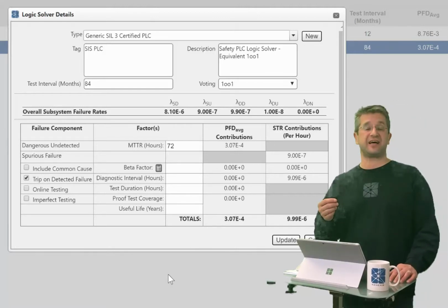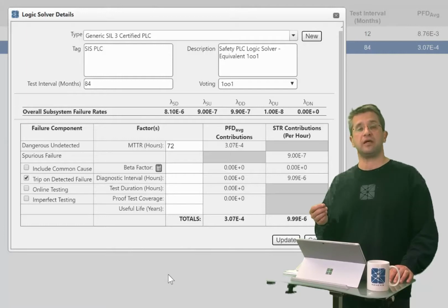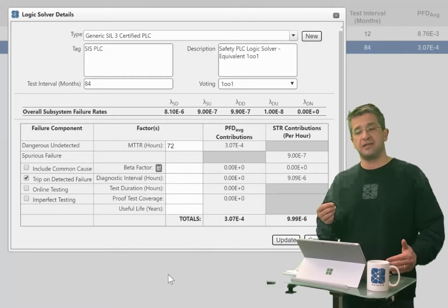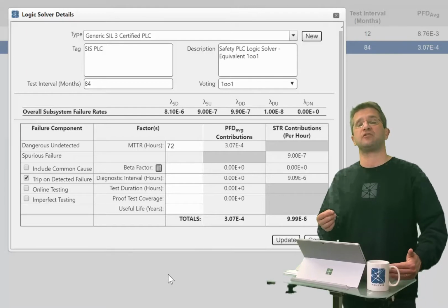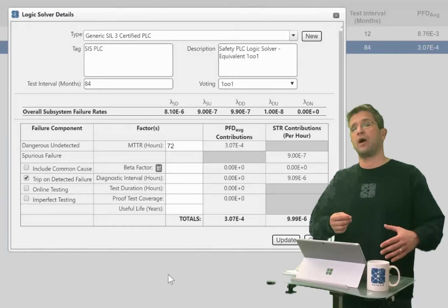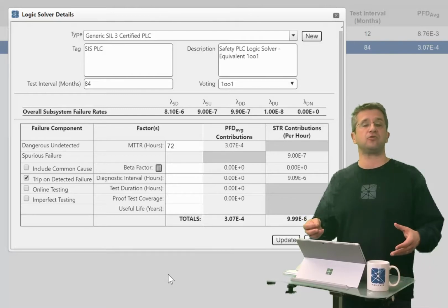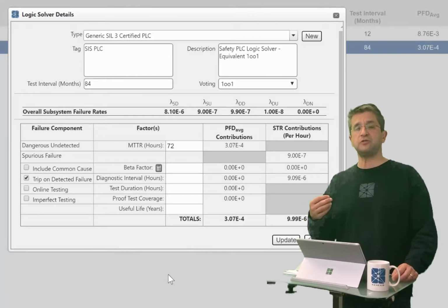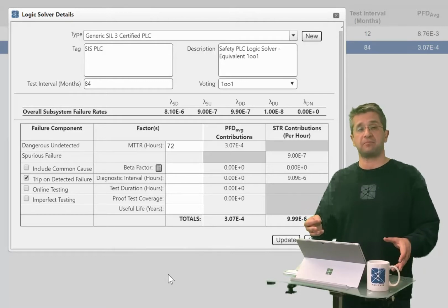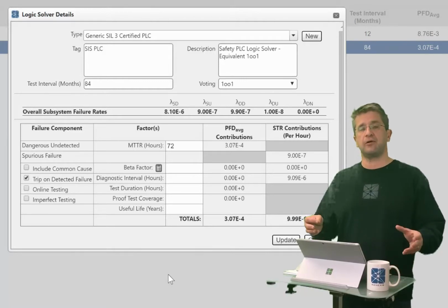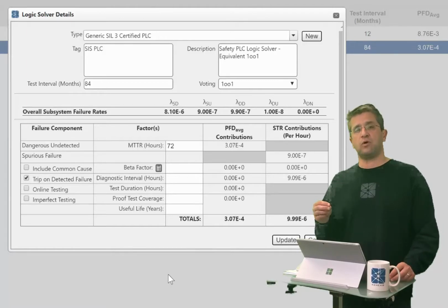The first one is highly recommended, and that is the black box model. So what you would do is you would go to your equipment vendor and have them perform calculations for their PLC system. This is actually what the equipment vendors prefer because their systems are so complex and hard to perform calculations on using standard tools. So once you receive the black box model data, you set up a black box model as described earlier, no problem. The second one is going to be the component approach.